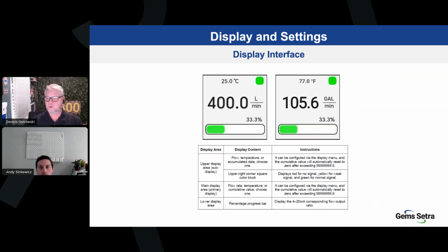We have a representation here of what you will see on the display. You have imperial as well as metric values that can be shown, or a combination of those. All of those are programmable separately in the device. Resolution you see there is to 1 decimal point. You can do whole numbers or 1 decimal point for tenths if you'd like. You can view the temperature either on the top, or you could have the temperature in the main display. You could have cumulative data either in the top or in the main. And then you also see the 4 to 20 milliamp progress bar at the bottom. The light in the upper right corner can be green, yellow, or red, and that's for signal strength. Of course, if you see yellow or red, it's time to get in there and check the parameters to make sure that you're matching your application correctly. Okay, next slide.